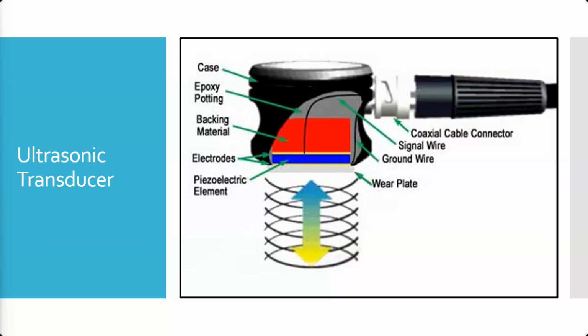It's potted inside of an epoxy compound, just to hold everything together and also to protect it from shock, like if you were to drop it. Wiring runs up out to your tester, and then on the face, you're going to have a wear plate right here, because the crystal itself, you don't want to be rubbing that against metals or other semi-abrasive materials. That wear plate typically is made of some kind of a metal, usually a steel. It can be an aluminum, but typically it's a fairly hard metal so that it wears well.